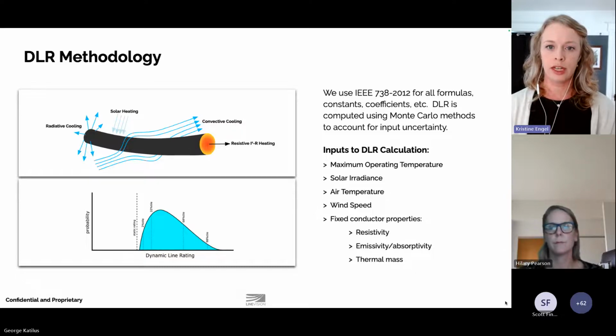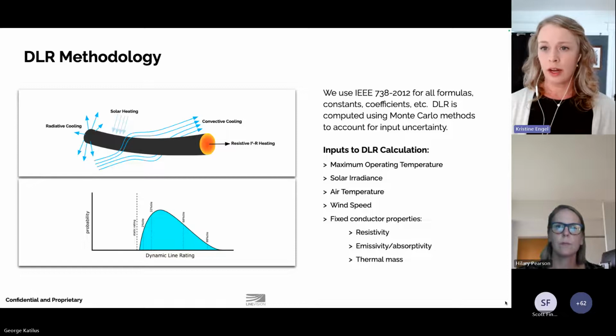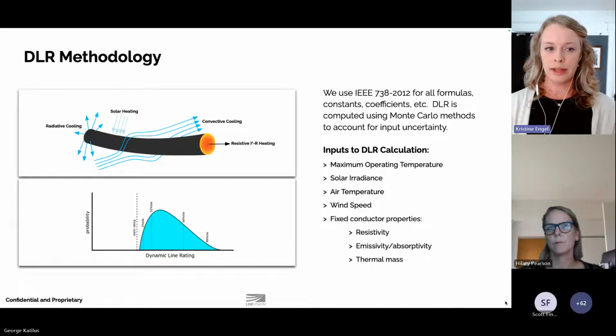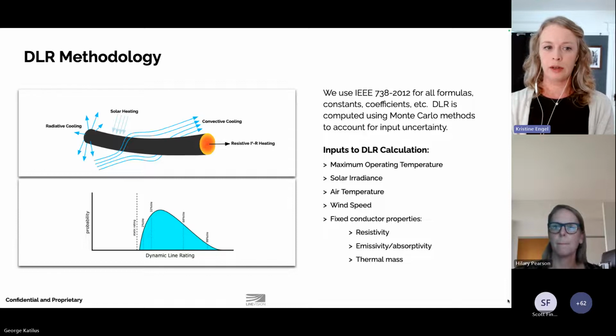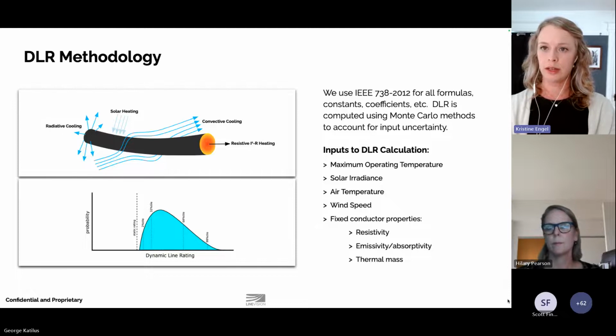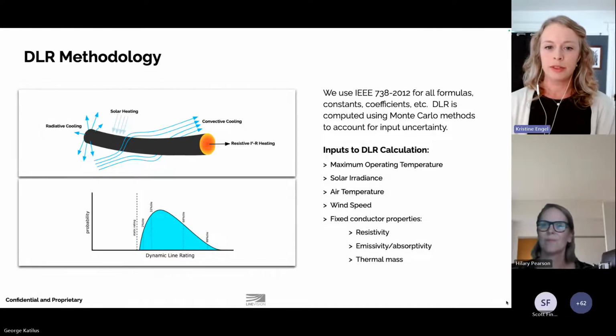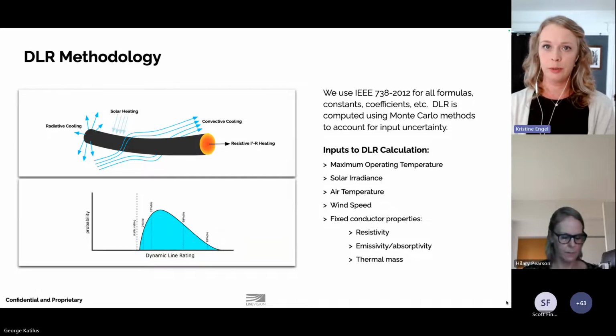We use the IEEE 738 heat balance equation for running our line rating calculation. And very importantly, we manage the uncertainty that is inherent to any measurement that you take, variable by variable, using a Monte Carlo simulation. So when we're defining the wind speed input to the line rating calculation, for instance, we're using not only the actual reported measurement of that wind speed, but also an uncertainty around that, a distribution.